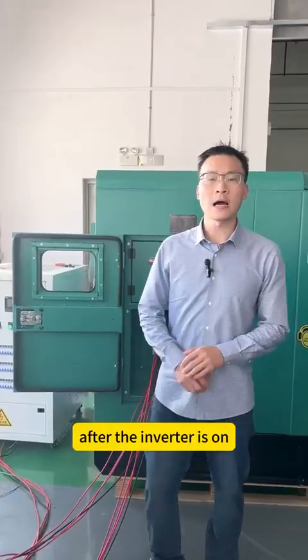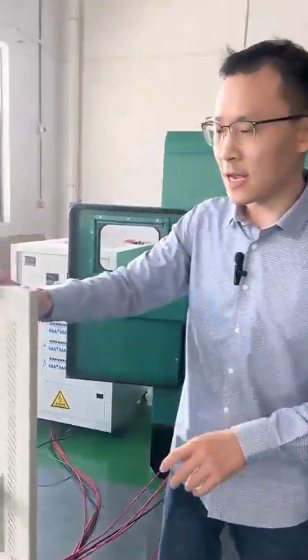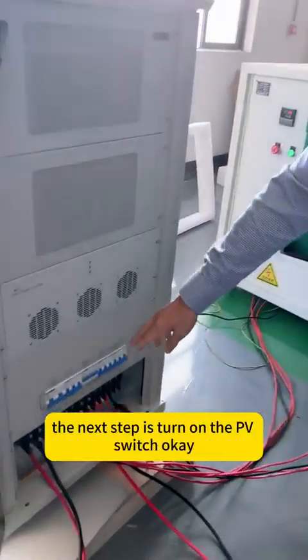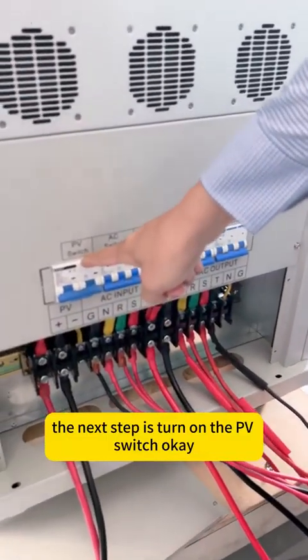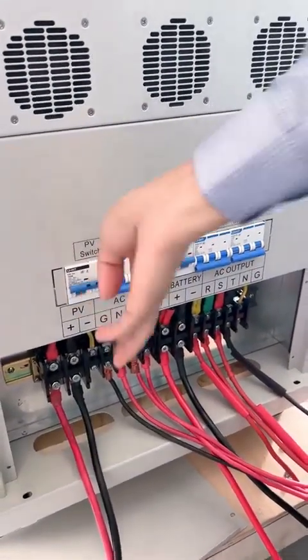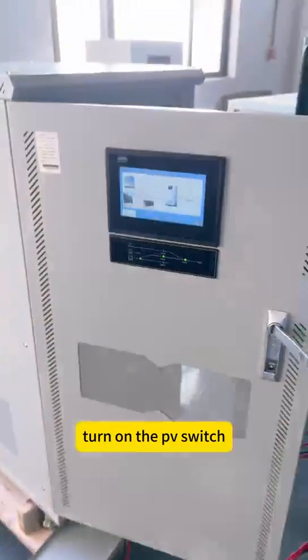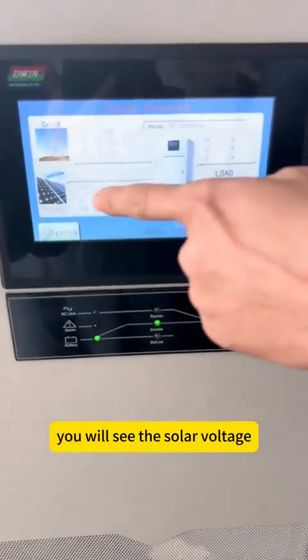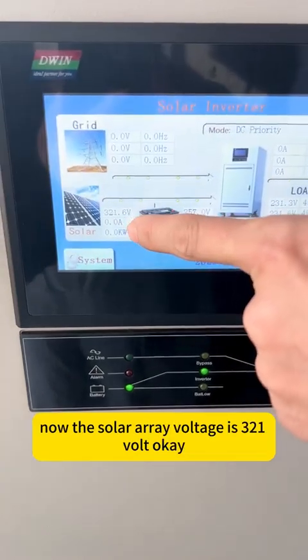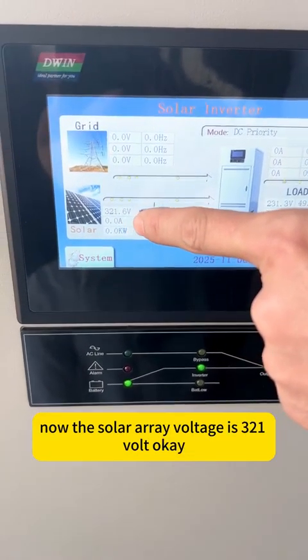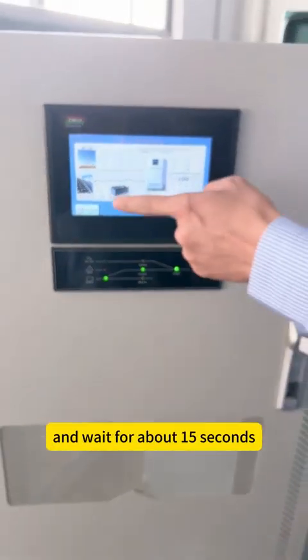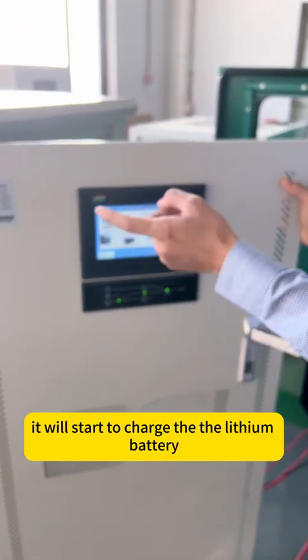After the inverter is on, the next step is to turn on the PV switch. Turn on the PV switch. Then on the screen you will see the solar voltage. Now the solar array voltage is 321 volts. And wait for about 15 seconds. It will start to charge the lithium battery.